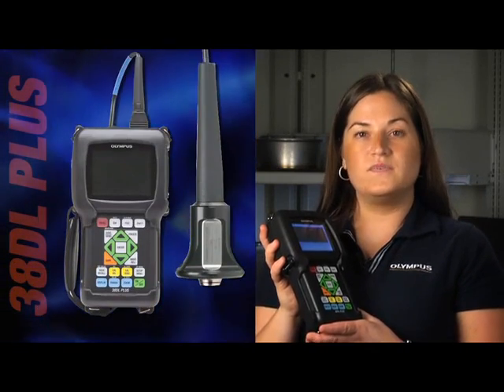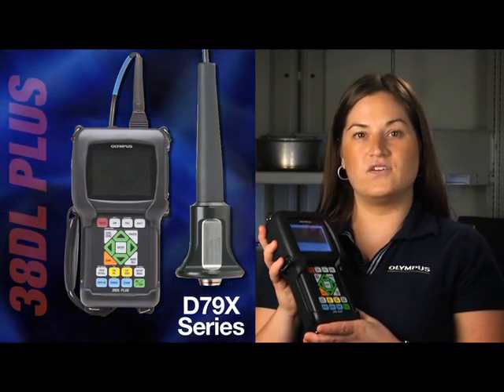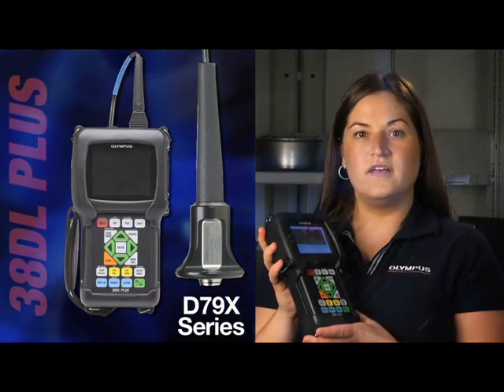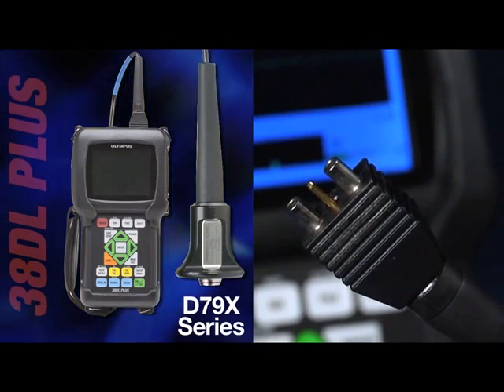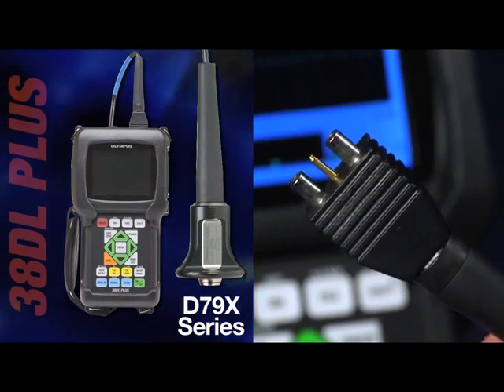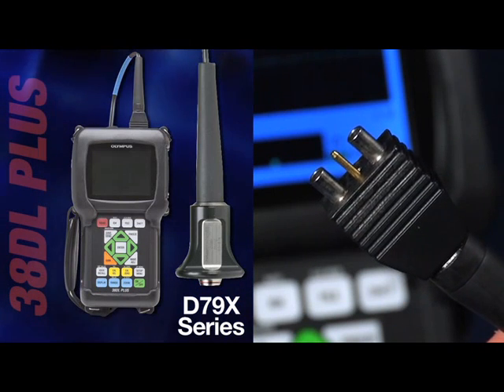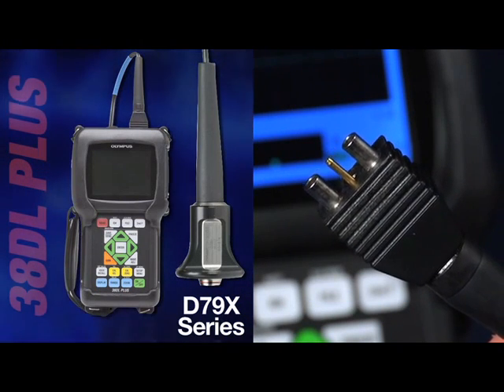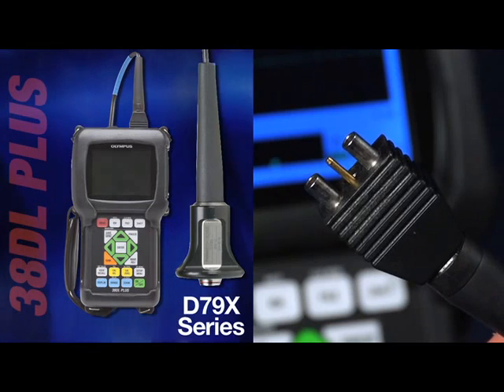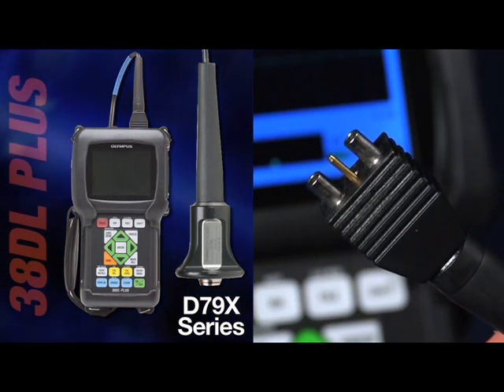Today we are going to discuss how to calibrate the 38DL Plus with a standard D79X series dual element transducer. These transducers have a center pin for probe recognition. Simply plugging them into the 38DL Plus allows the gauge to automatically recognize the transducer and recalls the default parameters for that probe.